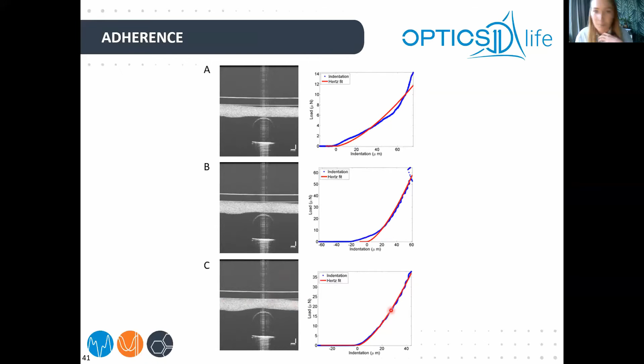So you also need to know the shape of your sample. For example, imagine this is some kind of hydrogel with some cells inside and has some kind of round shape. If we measure on this side of the sample, there's no issue for the cantilever to bend, nothing is going to touch it, all good. However, when we reach this area, we are on the other side a little bit. When we move the piezo down by this distance, we will start to push into the sample with the base of the cantilever. It will break the probe. Maybe, maybe not, but it's not good. Also, your load indentation curve would look strange, so it will give an indication that something is wrong there.